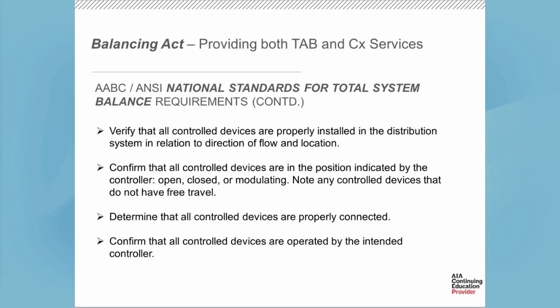And oftentimes the TAB firm has to go through and do that as part of their activities anyway. So it's very easy for them to verify that. Determine everything's connected properly, and moreover, this last statement here, confirm that all control devices are operated by the intended controller. This really means that the thermostat in room A is connected to the terminal unit that serves room A and not to the terminal unit that serves room B, which is served by another terminal unit. That's a very simple analogy, but if you've been in the business for any length of time, you know that these things get crossed all the time. And you could argue that it's the control vendor's responsibility to do this, but we see that that's not the case.